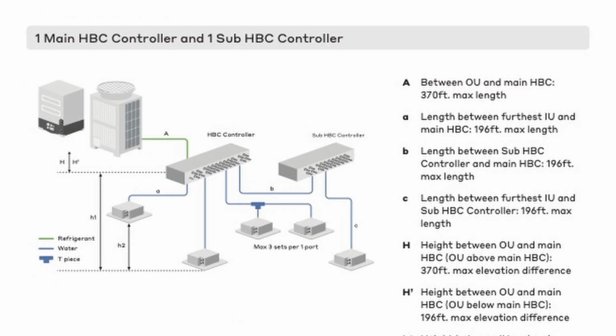So Mike and Tommy mentioned one other thing: the major difference from a planning and installation perspective is planning around the branch control box. It's larger. In addition to heat exchangers, you've got the chilled and hot water pump in there. There are drains that you need to account for. One of the most important things you can do is plan the location so that it's serviceable, so that you can get to the drain.